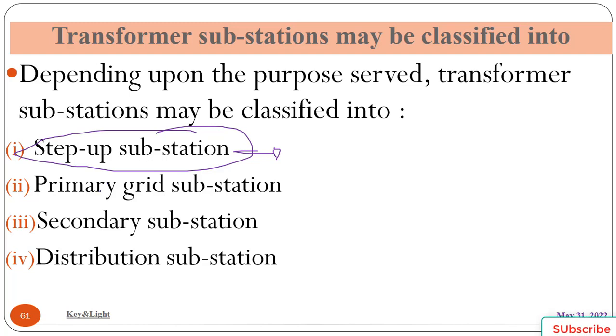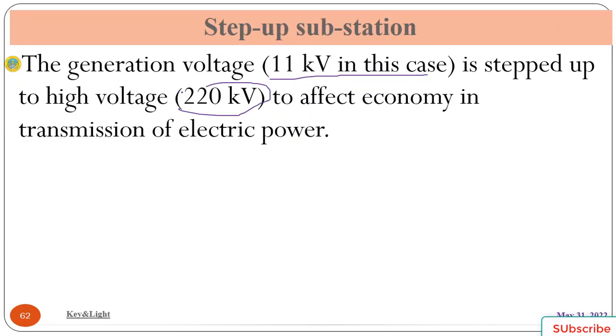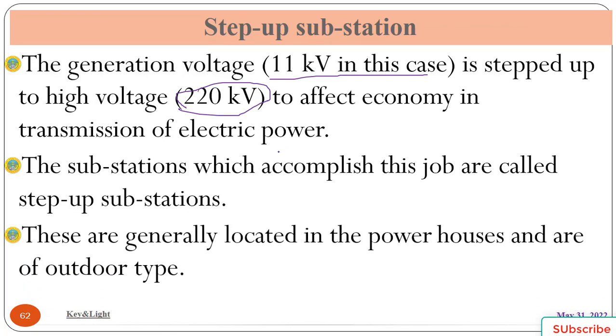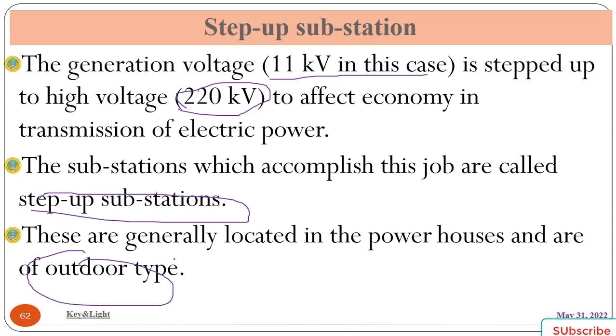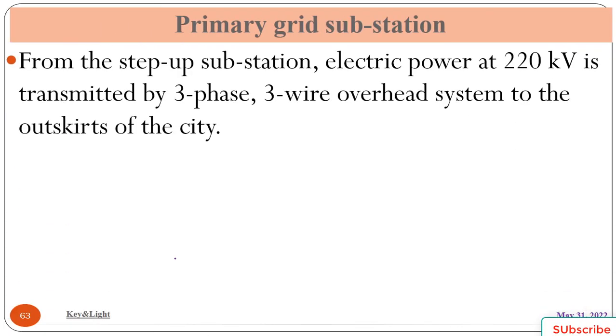In this case, a step up substation is a substation which gets the task to step up only. In this case, voltage is stepped up to 220 kV to affect economy in transmission of electric power. The substations which accomplish this job are called step up substations. These are generally located in the powerhouse and are outdoor type.